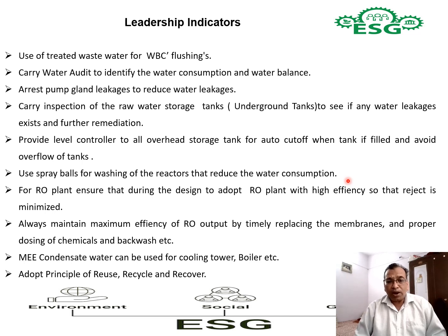Then for the RO plant, ensure that during design you adopt an RO plant with high efficiency so that reject is minimized. People usually see the capex amount, but you have to see it holistically. You have to adopt the better technology. Even if the initial capital investment is more, its merits in the long term are more, so that efficiency is maintained. So nowadays, based on recent technology, you have to use the latest high efficiency RO plants.